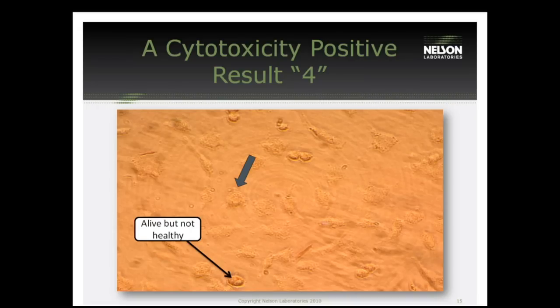A good cytotoxicologist can give you a hint of what kind of toxicity we're looking at, because we see so many cells and know the difference between a latex burn or chemical toxicity. If you get a good cytotoxicity technician, they'll give you a good indication of why you're failing. We won't be able to tell you exactly what it is, but at least we can investigate. MEM stands for Minimal Essential Media — the fluid we use to extract in, that serum and culture medium I mentioned. It's a media used to mimic what the body gives the cells, providing the minimally essential nutrients they need to grow. The test is named after that type of media.